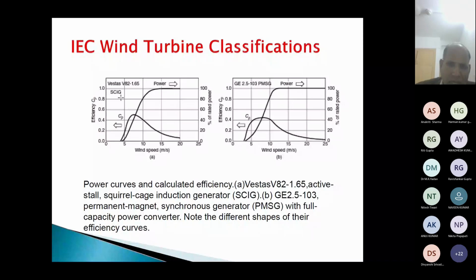In fact, this squirrel cage induction generator is a Vestas V82-1.65, which means the wind turbine rotor diameter is 82 and this individual generator is able to generate 1.65 megawatt. But it is squirrel cage induction generator technology, which means it is a type 1 generator. In this other case, you will see that it is a General Electric 2.5 megawatt with a wind turbine blade diameter of 103, and it is a PMSG, Permanent Magnet Synchronous Generator. So it is type 4 generator technology.